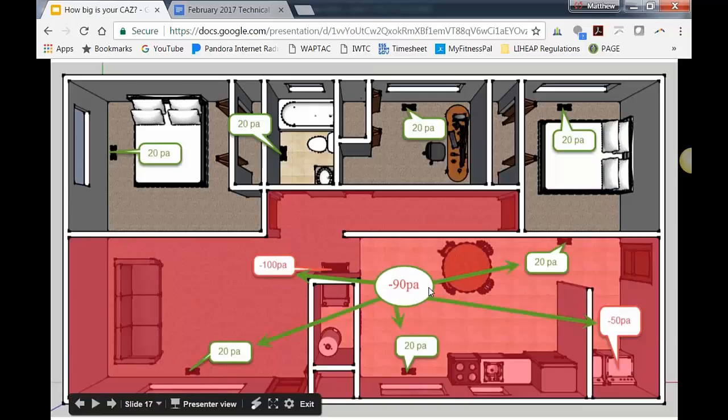And we essentially are doing that when we're doing a worst case test. You close that door and you watch the pressure. But that's not always perfect. You could close this door and watch the pressure, and then you could close this door, and maybe something going on in this zone also had an effect on this zone, which now has gone negative. So it's not perfect. It's not always going to be straightforward and simple.